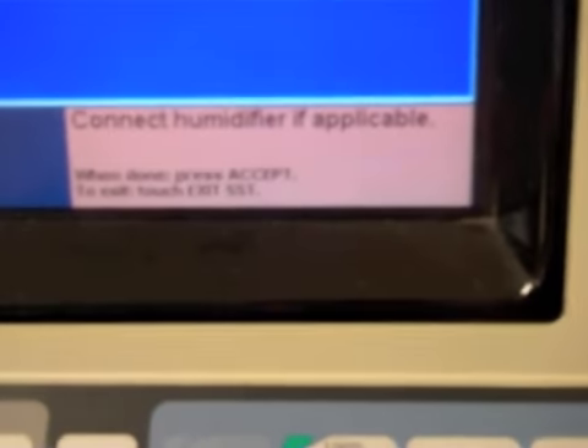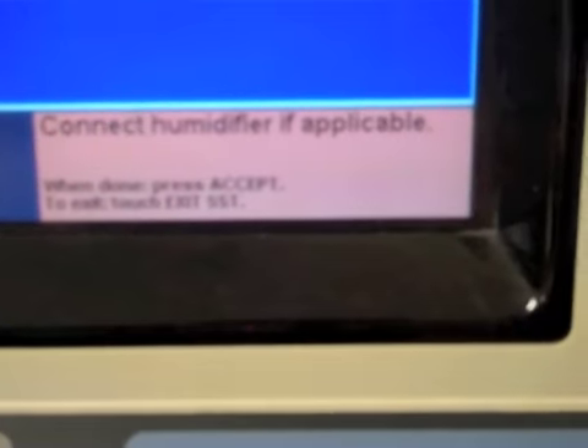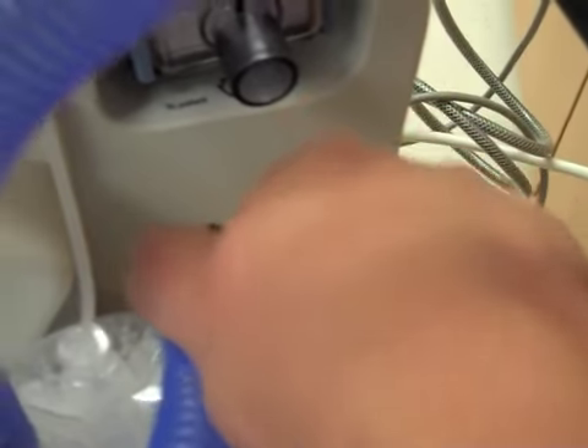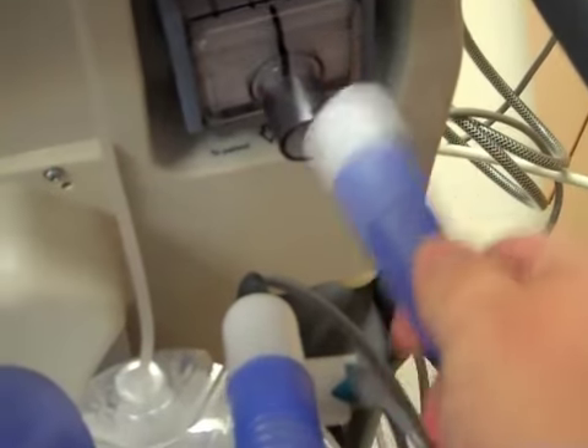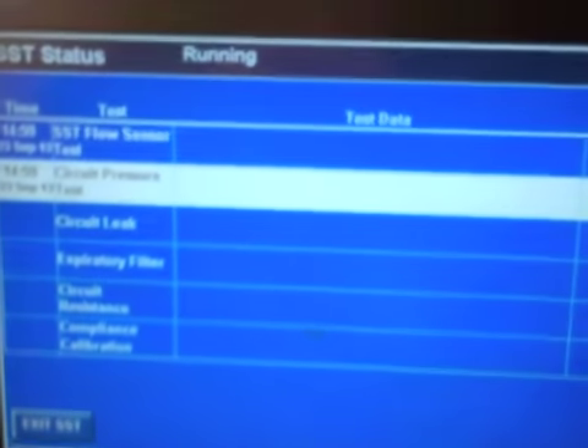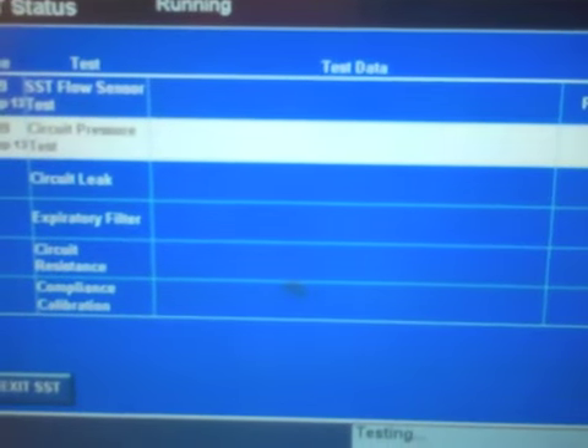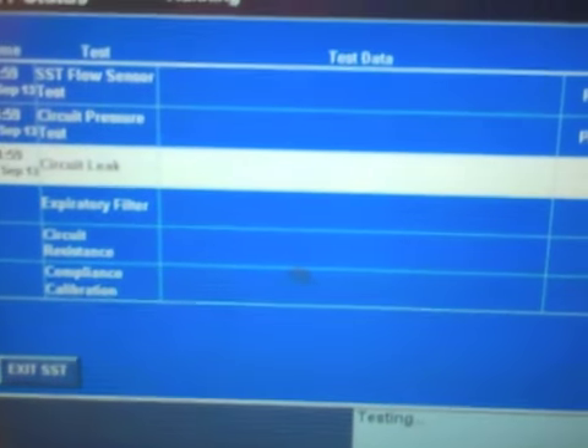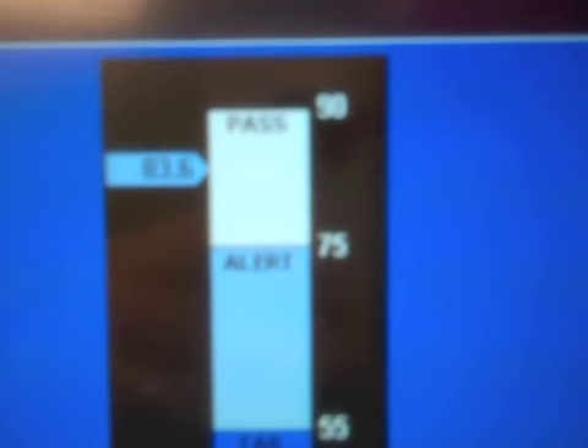Alright, down here now you can see it says connect humidifier if applicable. So I'm going to disconnect this, put it back on my humidifier, take my conduit and put that back on. Okay, hit accept. It's giving me a pass as a result for my flow sensor. It's now doing my circuit pressure test and circuit leak test. I want to be able to see that this is going to hold pressure. You want it between 75 and 90. This flag looks like it's around 83, so we should pass here.